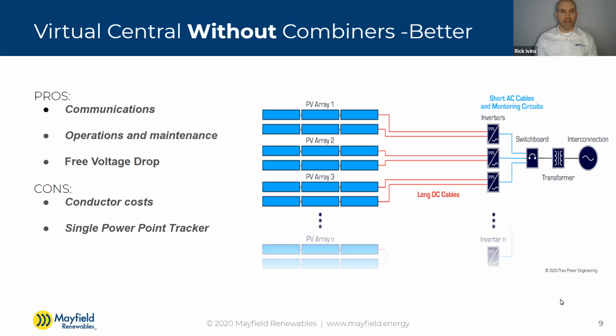Getting to some cons of this layout: the conductor costs. I said it's easier to manage voltage drop on the DC side because of the higher voltage, however these DC strings are likely copper - number 10, number 8, or even number 12 - they're not aluminum at that size. So they get a bit more expensive, whereas with combiner boxes you can output with aluminum, which is more cost effective than running all these small copper cables that could drive up the price.